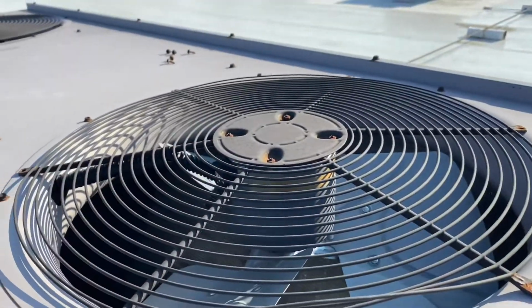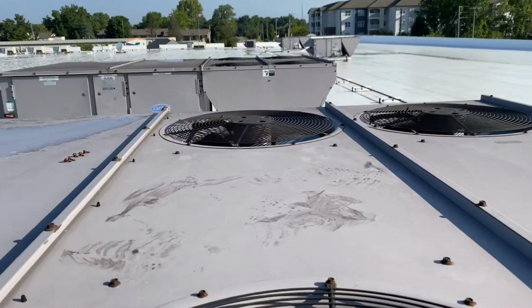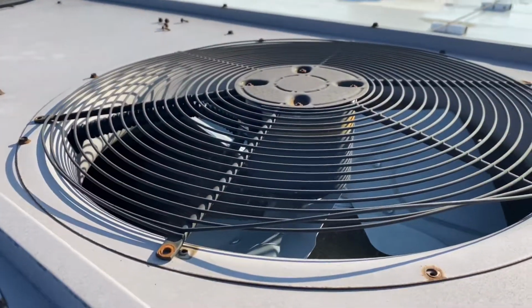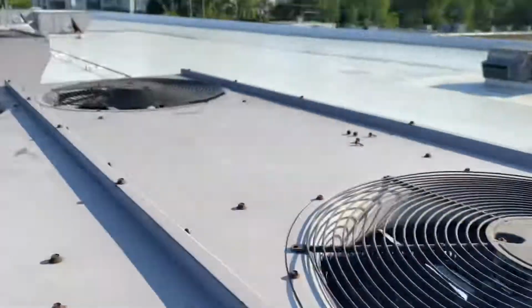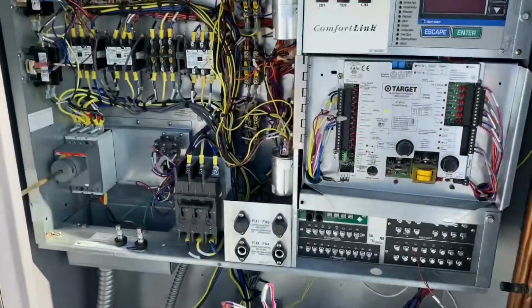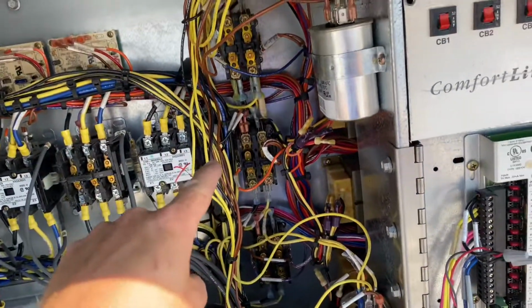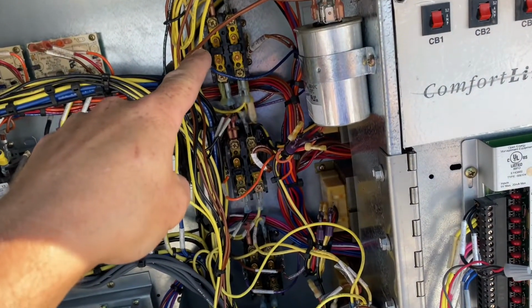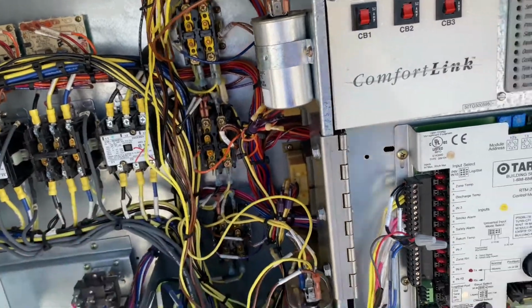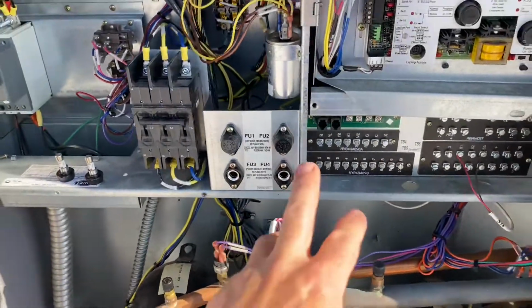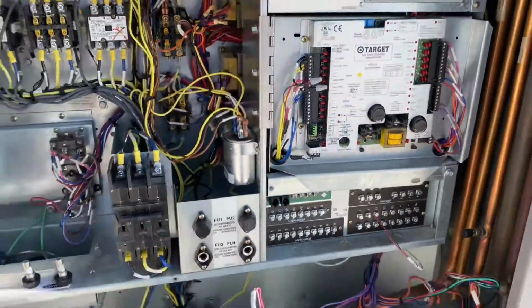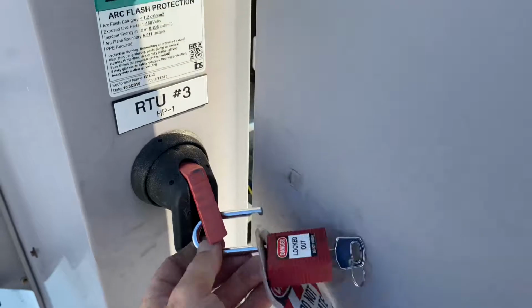Let's see. So I took out the bolts, screws for the grill covers, lifted them up enough to unhook motors 1 and 3. Got them unhooked. Came back down here, re-landed the wires for outdoor fan contactor 1 and outdoor fan contactor 2. Didn't need to replace the fuse because it was still good. And now I'm going to go ahead and power it back on and quickly get it into test mode.